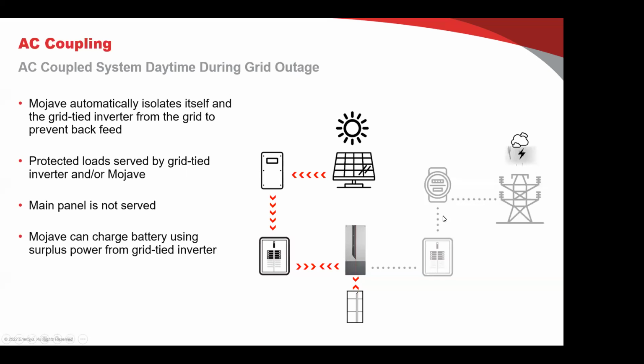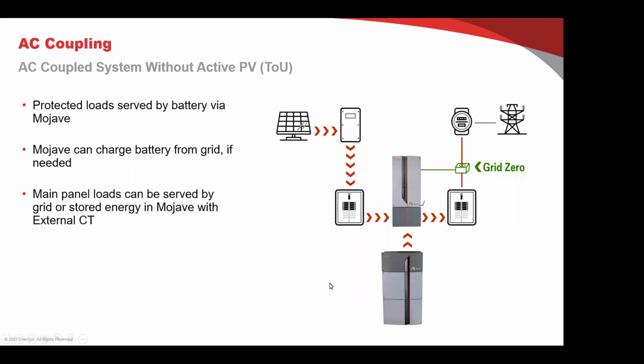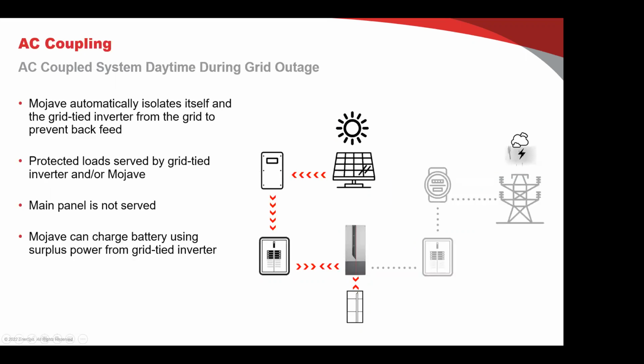The only exception might be if you had an auto transfer switch out here, and a grid, and you had a generator connected up. If you lose grid power and it switches over to the generator, and the generator starts, then yes, we would pass that generator power to the loads, and we could also use that generator power to charge the batteries if we chose to. That's the only case, because in that case we do sense that there's AC input, but if there's no AC input here, we can't backfeed. Yep. And because in the grid zero example, there's still the ability to backfeed the grid, that's why it can't happen under grid zero. Yeah, because if there's no grid here, we have to open the circuit. Our listing requires that. Gotcha. Thank you.